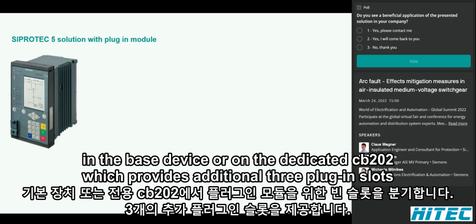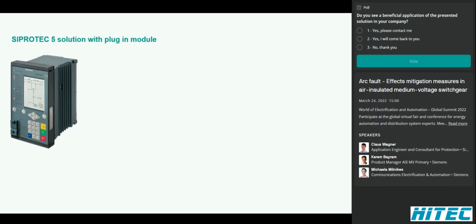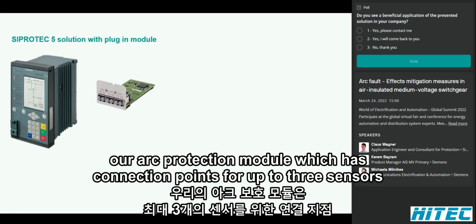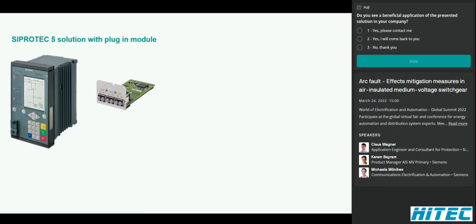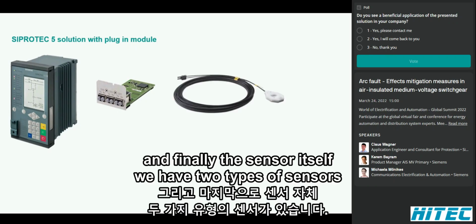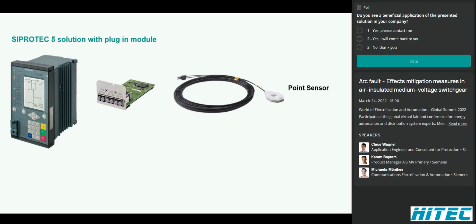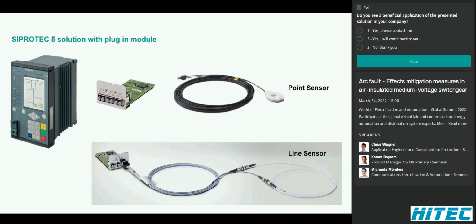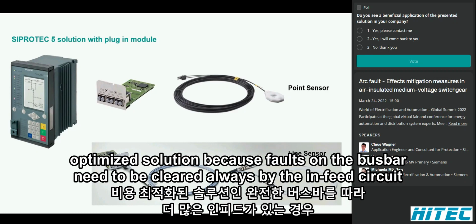An empty slot for a plug-in module in the base device, or on the dedicated CB202, which provides additional 3 plug-in slots. Our arc protection module, which has connection points for up to 3 sensors. And finally, the sensor itself. We have 2 types of sensors. A point sensor, which can be placed in one compartment of the switchgear, or a line sensor, which can be placed, for example, along the complete busbar, which is a cost-optimized solution because faults on the busbar need to be cleared always by the in-feed circuit breaker or breakers if we have more in-feeds.